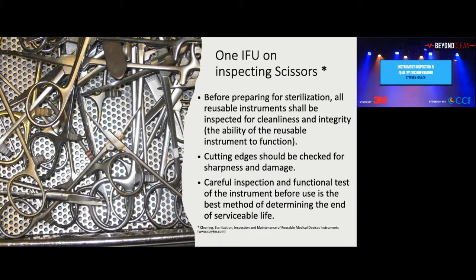One IFU on scissor inspection: before preparing for sterilization, all reusable instruments shall be inspected for cleanliness and integrity, the ability of the reusable instrument to function. Cutting edge should be checked for sharpness and damage. Careful inspection and functional tests of the instrument before use is the best method of determining end of serviceable life. So they might not tell you how, but you'll use your critical thinking skills, you'll use standards, guidelines, peer-reviewed literature, and you'll come up with the best way to test those scissors or whatever it is each and every time. And again, I'm going to use that as a specific example later to try to tie this all in.